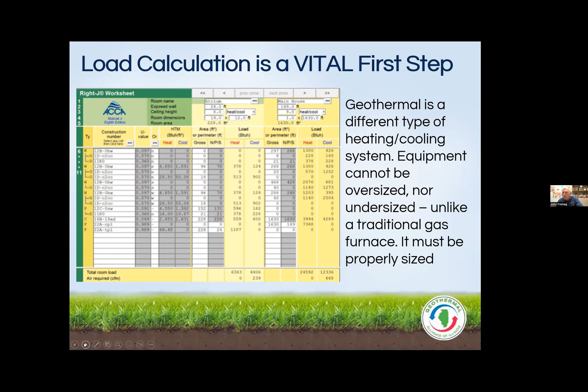You wouldn't want to do that with geothermal. For one thing, oversized systems are too expensive to install, and second, they won't operate properly because they won't provide proper dehumidification. So you want to size the load correctly—walking through the home or business to determine the heating and cooling needs. The first step is to run a good load calculation using load calculation software, going room by room to measure those needs.